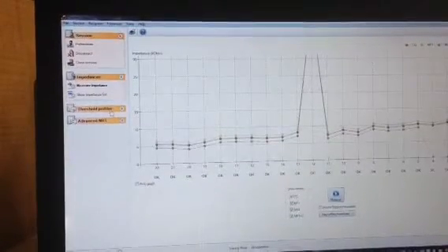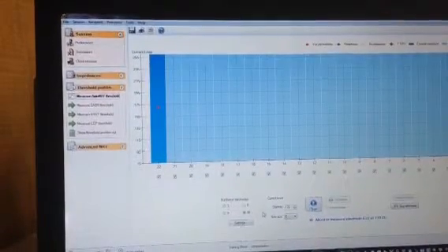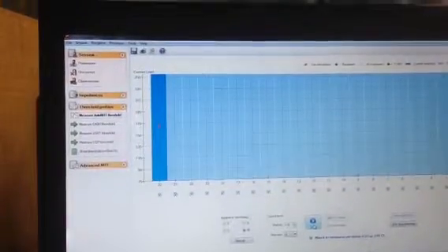After you've done that, the next step that you need to do is measure auto NRT. You will see measure auto NRT. You are doing it on all channels. The starting level is 170. All you need to do is press start.